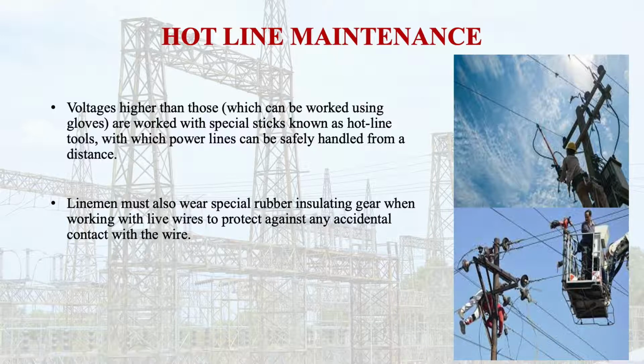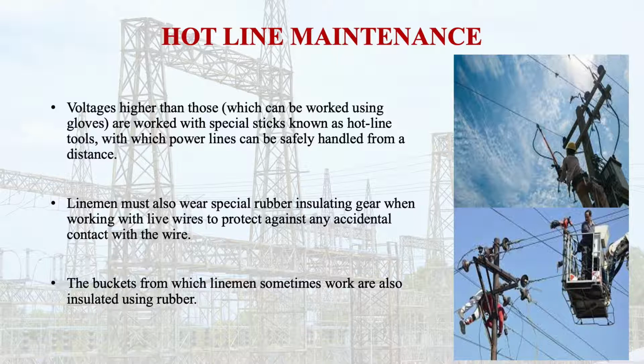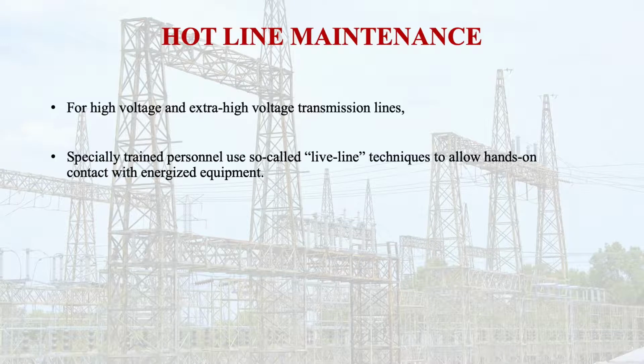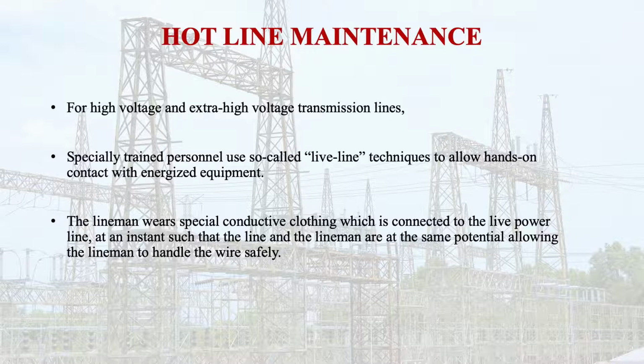Linemen must also wear special rubber insulating gear when working with live wires to protect against any accidental contact with the wire. Buckets from which linemen sometimes work are also insulated using rubber. For high voltage and extra high voltage transmission lines, specially trained personnel use so-called live line techniques to allow hands-on contact with energized equipment. In this case, the worker is electrically connected to the high voltage line so that he is at the same electrical potential, and the lineman wears special conductive clothing which is connected to the live power line, such that the line and the lineman are at the same potential, allowing the lineman to handle the wire safely.